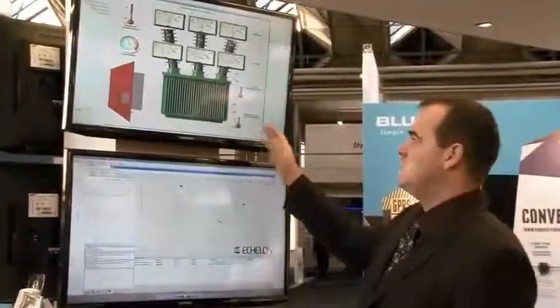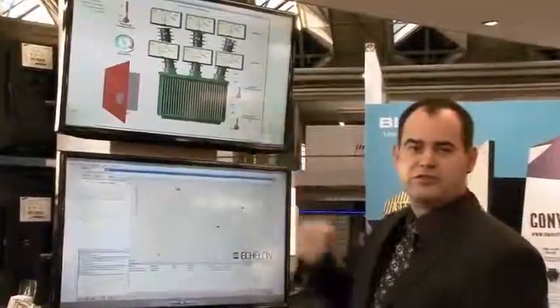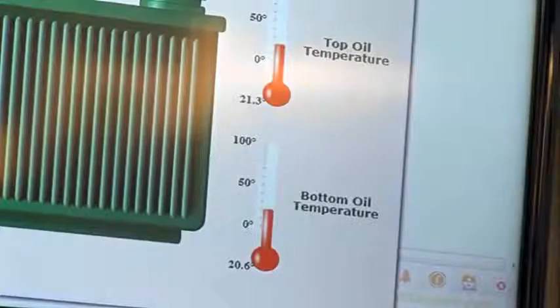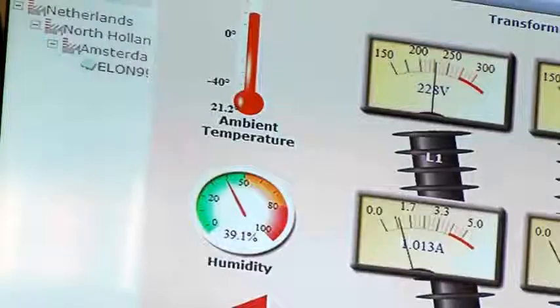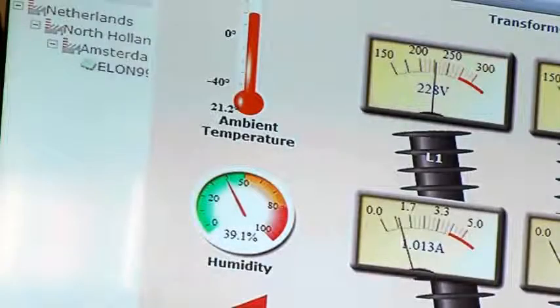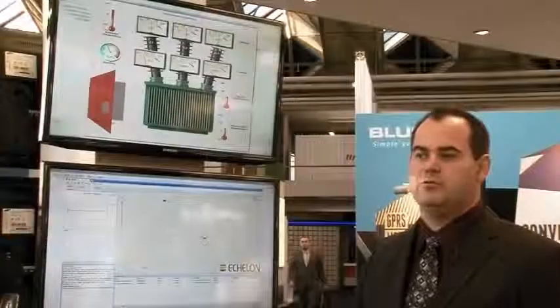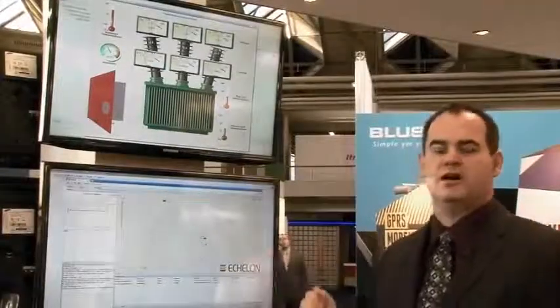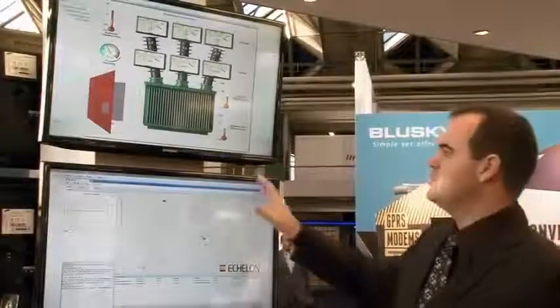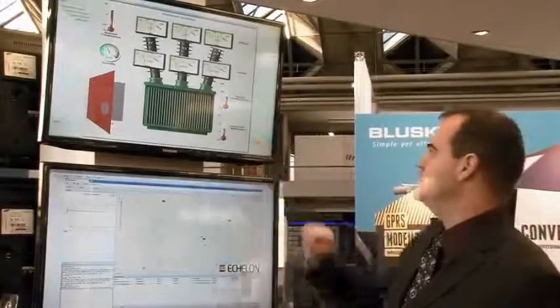We have the three different temperature sensors that I showed before — the bottom oil temperature, top oil temperature of the transformer, as well as the ambient temperature and the humidity. With this information we can correlate the data and see if there is a discrepancy from the expected temperatures of the transformer in those situations.